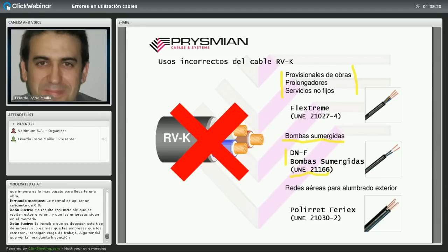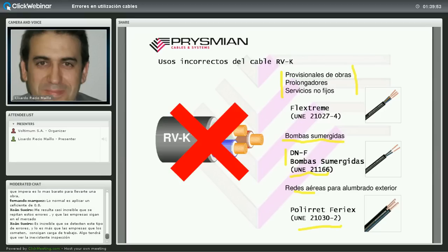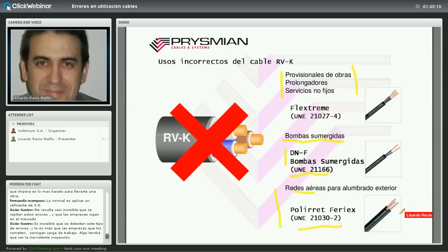Para redes aéreas de alumbrado exterior se necesita el cable tipo Polirret (cables trenzados aéreos de cobre según UNE 21.030, parte 2), según exige expresamente la ITC-09 del reglamento. El cable RVK tampoco puede grapase directamente a la intemperie: el reglamento, desde la ITC-30.2, asimila todas las intemperies a locales mojados, por lo que el cable debe ir bajo canalización estanca aunque la norma del cable lo permita en exteriores.